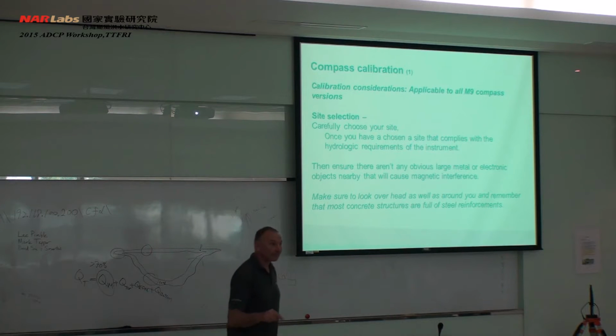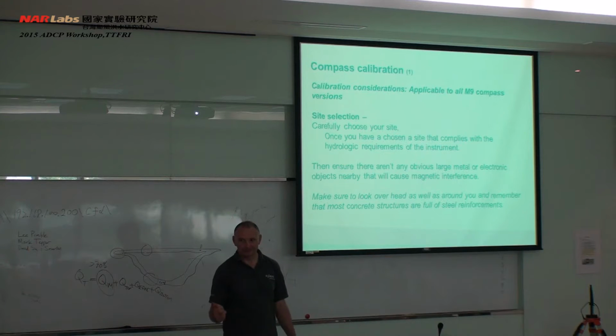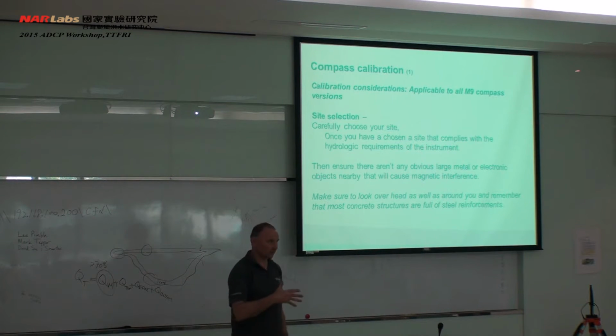That said, an instrument where you're using bottom track only, sorry, I haven't talked much about bottom track and the track references, but the instrument checks how it's going across the channel by using either bottom track or the GPS. An instrument that is using bottom track only can still do a discharge measurement without a good compass calibration. It becomes critical to have a good compass calibration when we are using GPS.